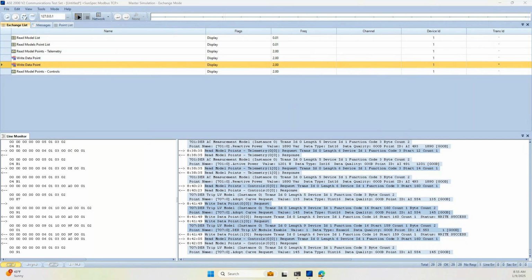And IEEE 2030.5 supports permanent connection if required. That means the protocol is designed for intermittent connection failures or interval-based connections, but it also supports permanent connections. Some utilities demand permanent connections. Here in California, we are using permanent connections unless there is a cellular network problem. The connections are retained from the site gateway to the DERMS system. So the connection is very reliable over 5G, 4G or LTE networks, and you'll be able to get the monitoring and controlling done as if it is a SCADA protocol.